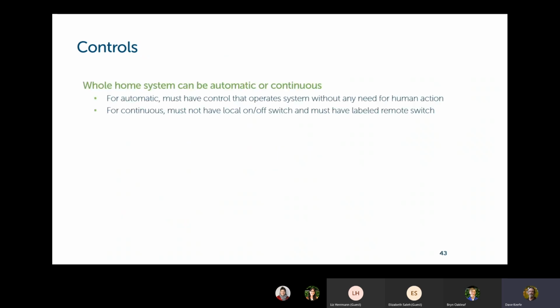The code says you have to have some controls that are capable of running the system regardless of what the humans do. So you can't have any system that requires people remembering to turn things on or off. You can do automatic, you can do continuous. For automatic, we're basically talking about timers. So some kind of control that turns things on, turns things off according to some prescribed program schedule. You can, if you choose, run your ventilation system continuously rather than automatically. Continuous means just exactly like it sounds. It runs all the time.